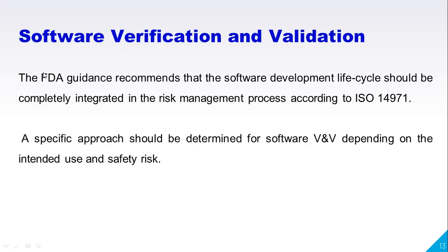Even a minor bug in the software makes it give negative results. We have observed such consequences. So in order to avoid that, careful verification and validation of software is needed, much more than for mechanical. In the case of mechanical, if the machine does not work properly, we can correct it. But it is not like that with software. So utmost care should be taken.